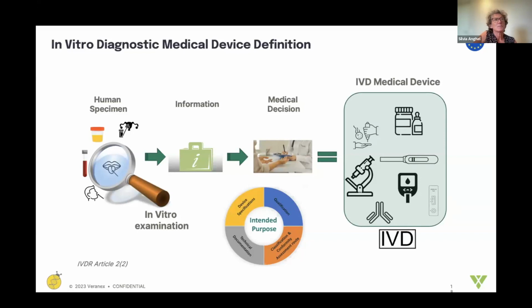So overall in Europe, tests used for the purpose of diagnosis must comply with the applicable regulation, which since May 26, 2022, is the in vitro diagnostic regulation, also called IVDR. One of the first steps in knowing if the IVDR is applicable to a test is to assess whether the device will qualify as an IVD. A test will qualify as an IVD based on its intended purpose, or as Sheila explained, intended use, and will only qualify as an IVD if it fulfills the following conditions. The examination is conducted on human samples, the examination is conducted in vitro, and the result of the test provides information which will be further used to take a specific medical decision.